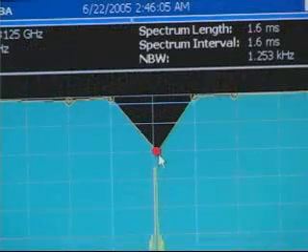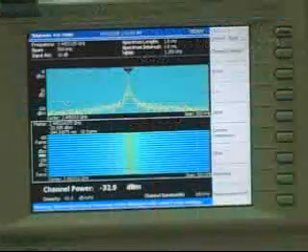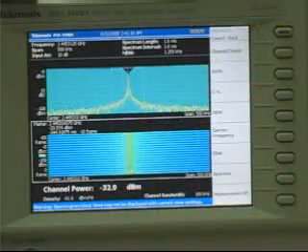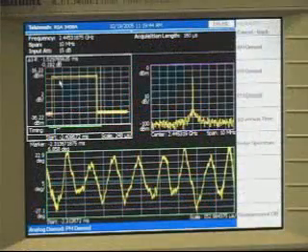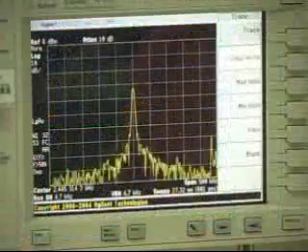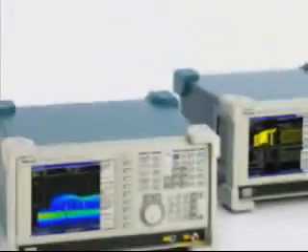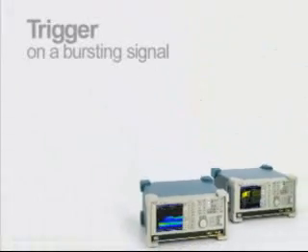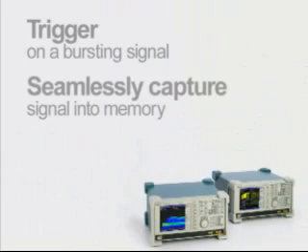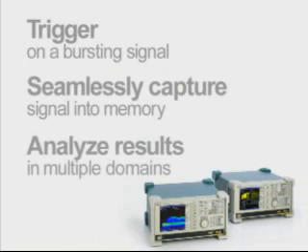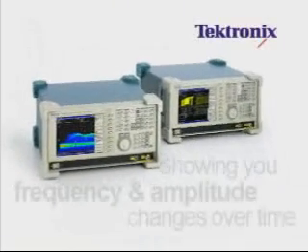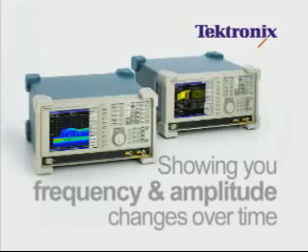The ability to trigger on a bursting signal, seamlessly capture the signal into memory, and analyze the results in multiple domains is something you can't do with a swept spectrum analyzer. These capabilities enable the Tektronix RTSA to greatly reduce the time it takes to characterize and troubleshoot transient RF signals by showing you frequency and amplitude changes over time.